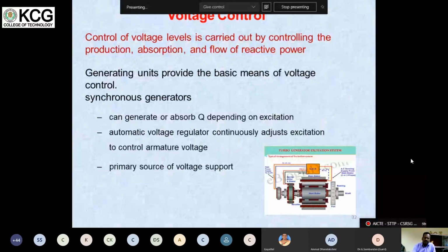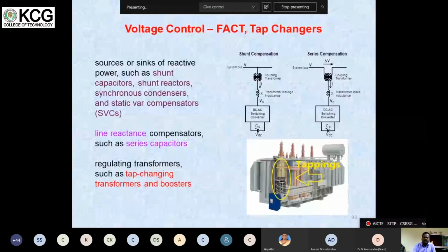There are two factors to be controlled in the grid system to maintain the grid discipline. And of course, we discussed about FACTS devices also: series compensators, static VAR compensators, series capacitors, and tap changing transformers or boosters, also used for voltage control. If the voltage is more, then we have reactors. If the voltage is less, we have capacitors. We have two types of capacitors normally: the shunt capacitor and the series capacitor. Series capacitors are used in the transmission line to have a progressive increase in the voltage.